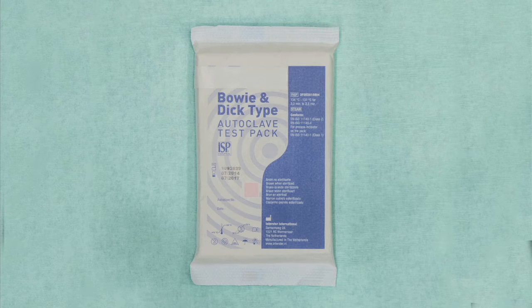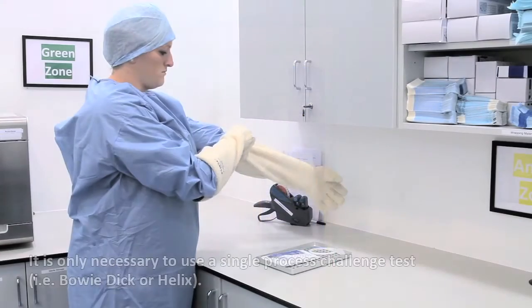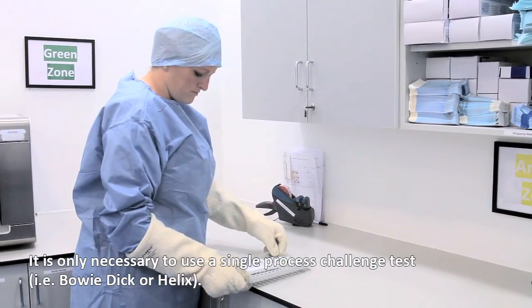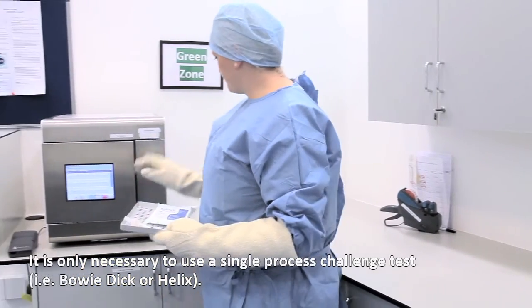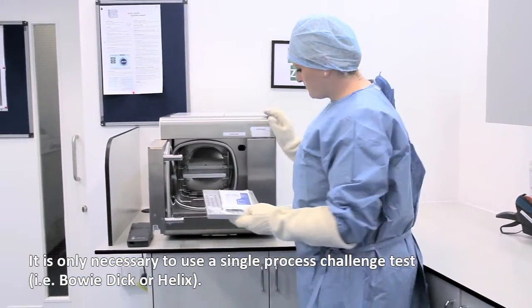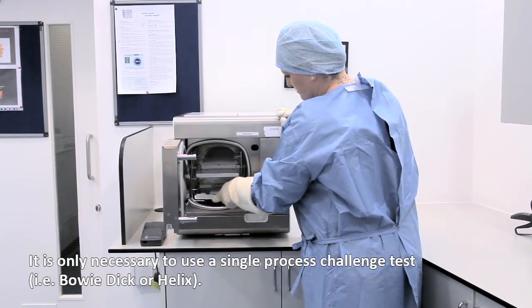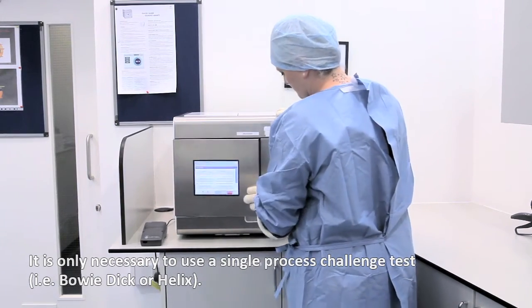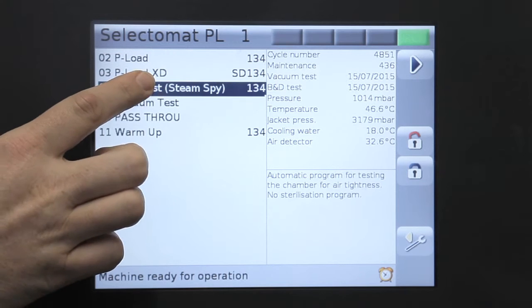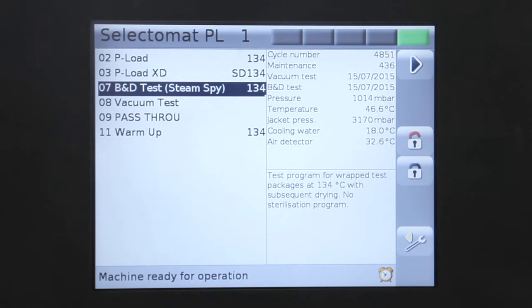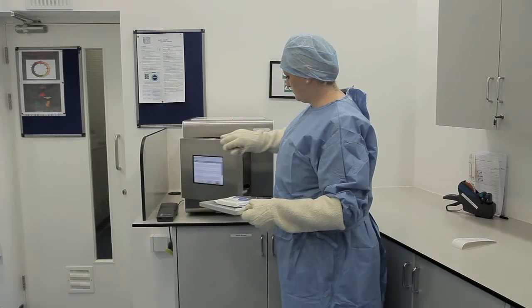The third test to be completed is the Bowie and Dick test, which monitors an even distribution of steam penetration within the autoclave chamber during the cycle. The Bowie and Dick test must be carried out on a daily basis. The test pack is placed on a tray into an empty autoclave, run on a dedicated cycle called a Bowie and Dick cycle that is 134 degrees centigrade for 3.5 minutes. The Bowie and Dick test can signal the presence of non-condensable gases. Inadequate air removal manifests as air pockets in the indicator, showing a failure of the test.